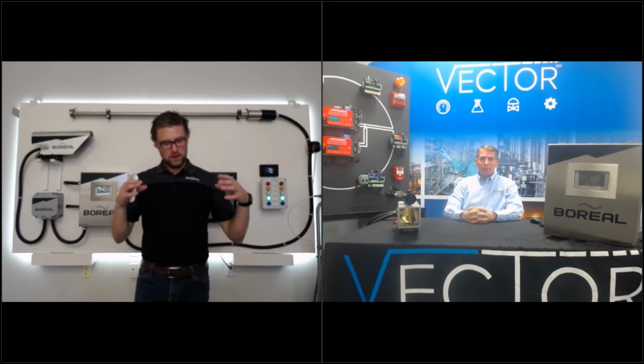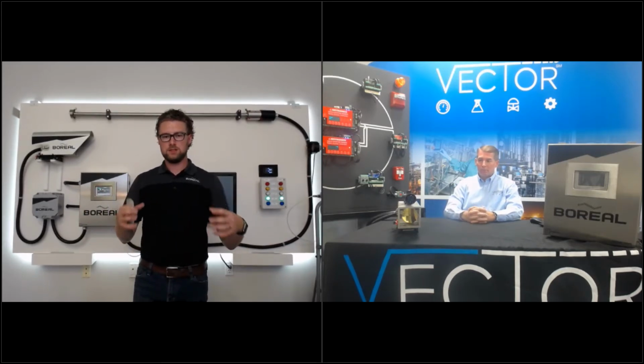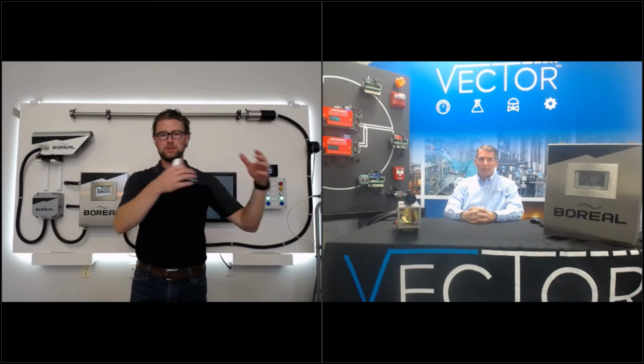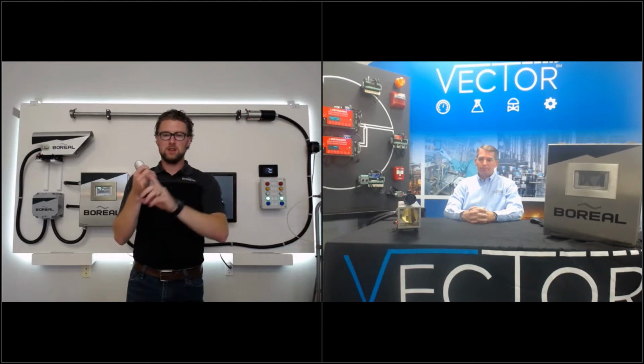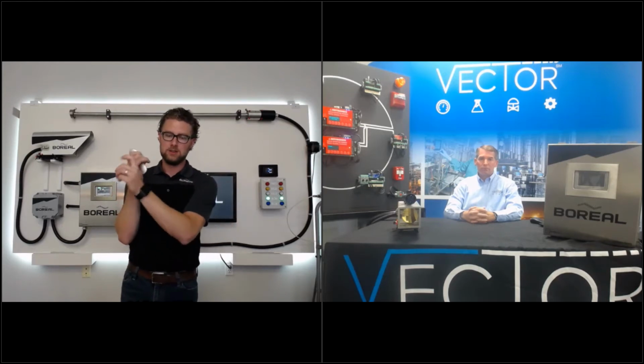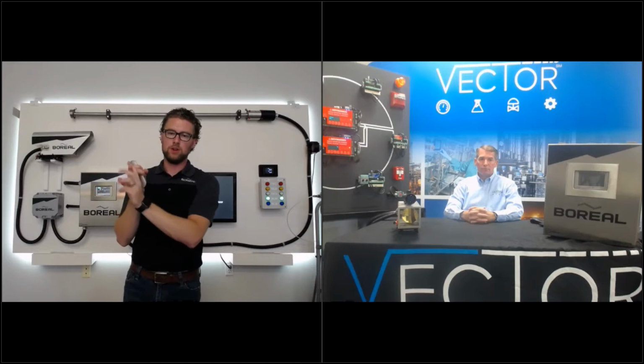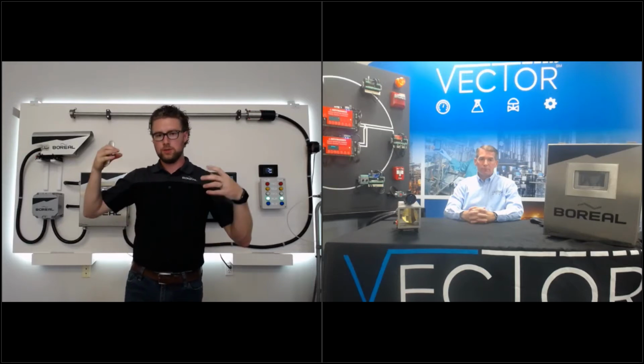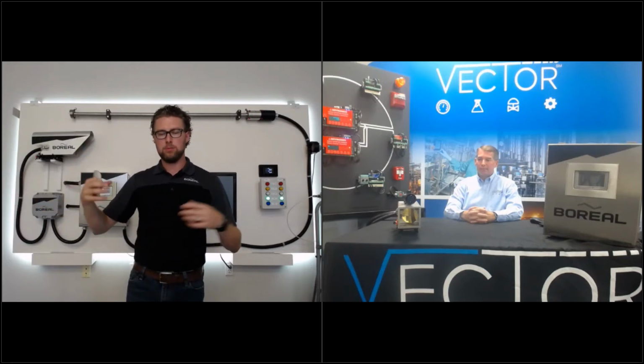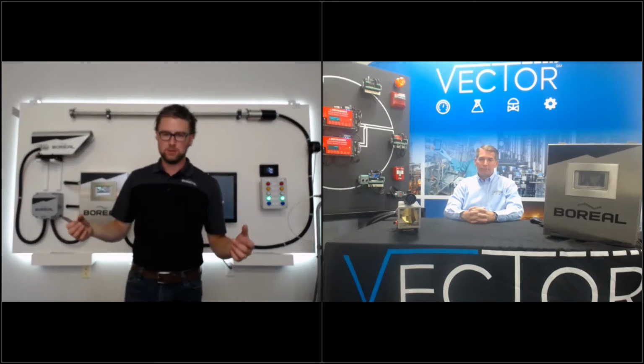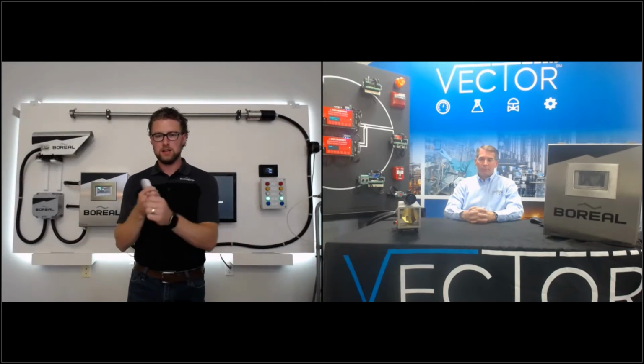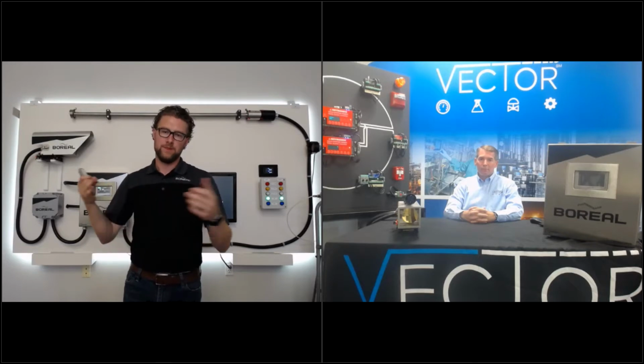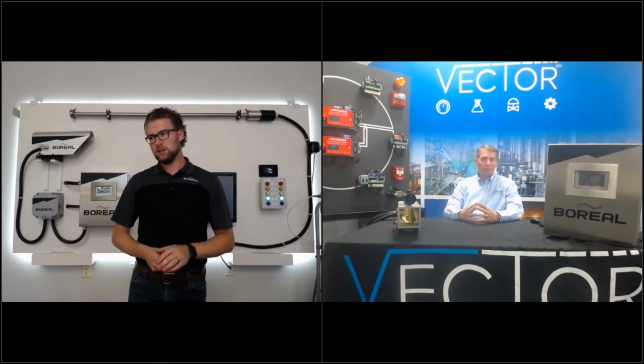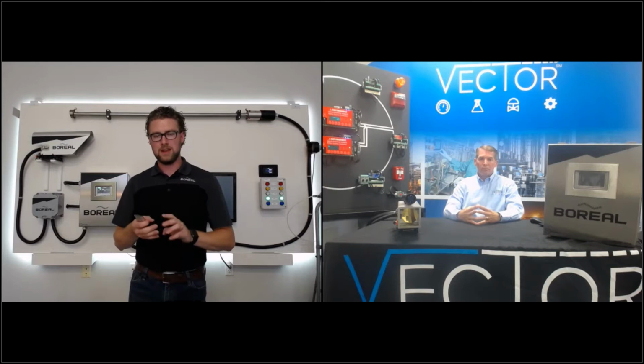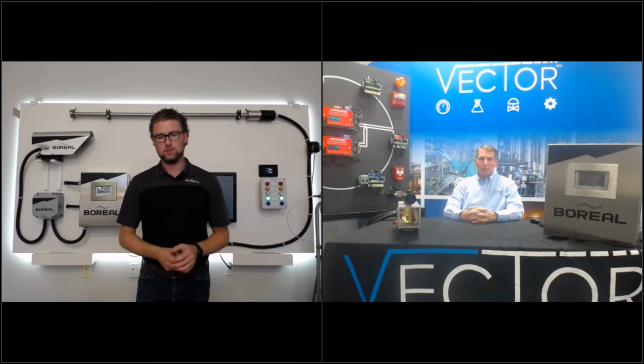So it is vitally important for your safety system to be as effective as possible. You have to have the best possible sensing elements to maximize the likelihood of detecting that loss of containment or the leak. Plus, you want to do it as fast as possible, so those executive actions carried out by your safety system can happen as soon as possible, because the faster we detect a leak, the faster we can act. And the faster you act, the odds of protecting people, personnel, and assets increase as well.